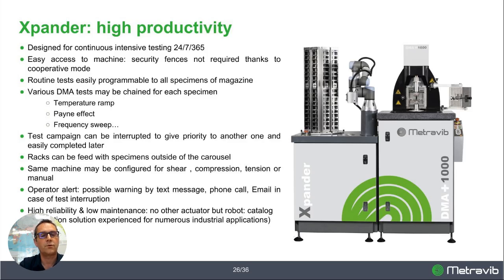Routine tests can be easily programmed for all specimens of the magazine. So various tests can be combined and chained for each specimen. It means that for one single specimen, you can chain a temperature ramp, a payne effect test, a frequency sweep. The combination of tests is really free and flexible. A test campaign can be interrupted to give priority to another one, and because that's a real life case for a tire manufacturer, it's quite easy to complete the former test campaign later.